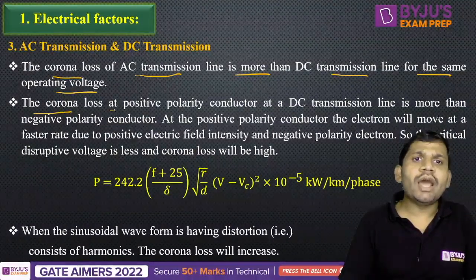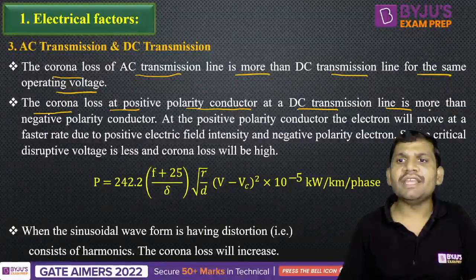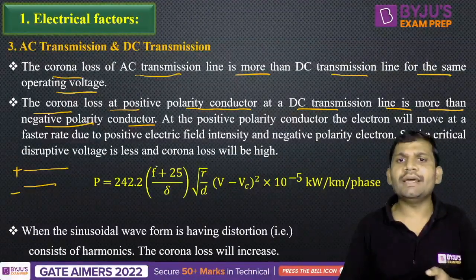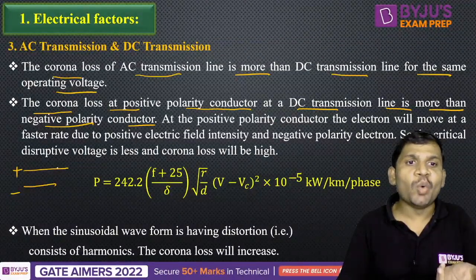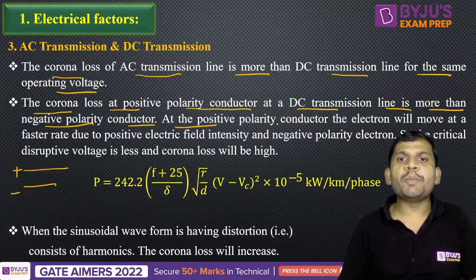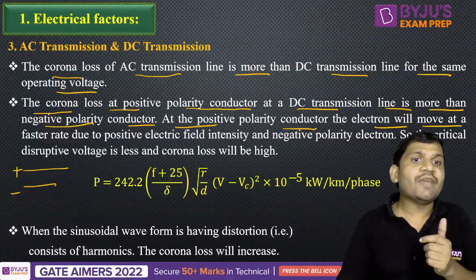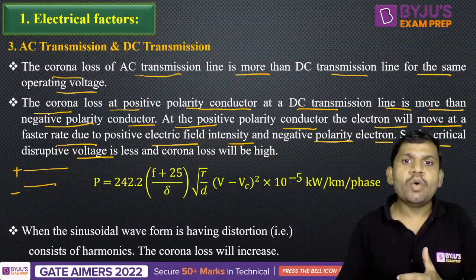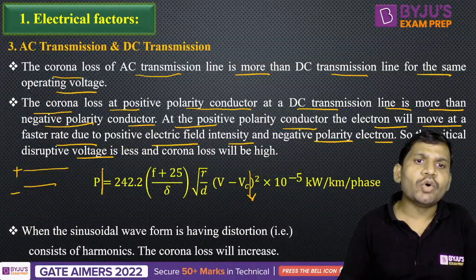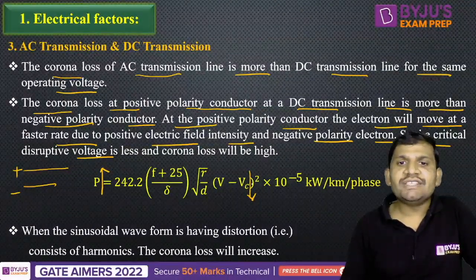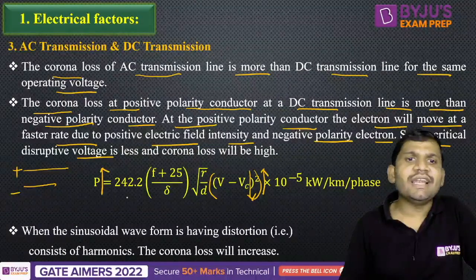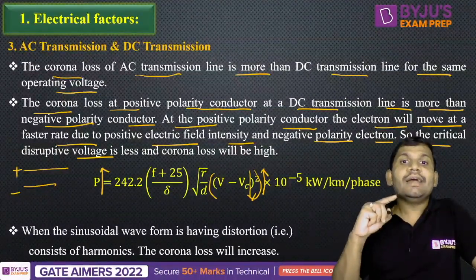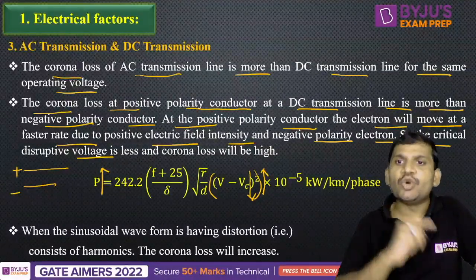One more point to remember: the corona loss at positive polarity of a conductor in a DC transmission line is more than at the negative polarity conductor. In a DC transmission, there is a positive conductor and a negative conductor. At the positive conductor, the corona loss is more because the electron moves at a faster rate due to the positive electric field intensity, so the critical disruptive voltage is less. When the critical disruptive voltage is less, the corona loss is high — if Vc is reduced, V minus Vc increases, and power loss increases.